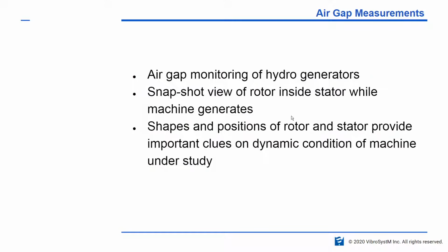Okay. So air gap monitoring of hydro generators gives you a snapshot view of the rotor inside the stator while the machine generates power. So it replaces the need to take all these static readings that, historically, people have been taking for years and years. Although in some cases the readings are very, very precise, basically what it tells you is what the shape and the position of the rotor and stator are when the unit is stopped and cold. It doesn't produce a lot of power there.